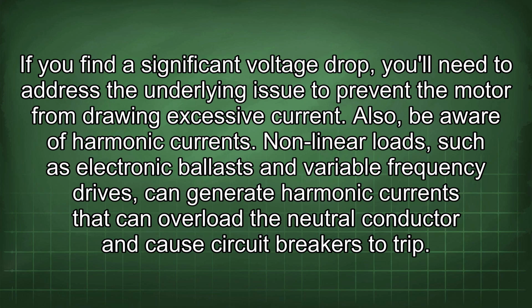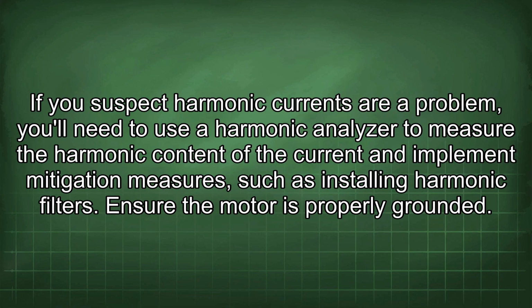Also, be aware of harmonic currents. Nonlinear loads such as electronic ballasts and variable frequency drives can generate harmonic currents that can overload the neutral conductor and cause circuit breakers to trip. If you suspect harmonic currents are a problem, you'll need to use a harmonic analyzer to measure the harmonic content of the current and implement mitigation measures, such as installing harmonic filters.